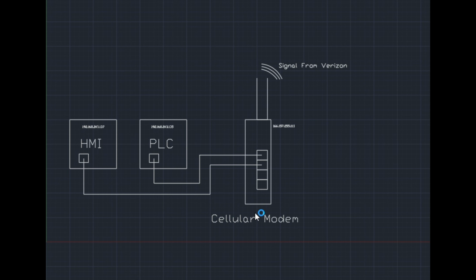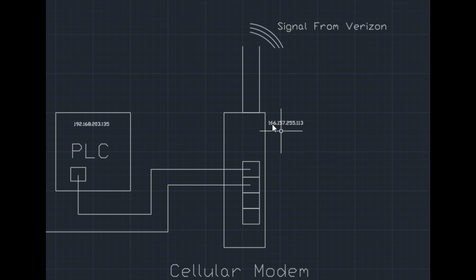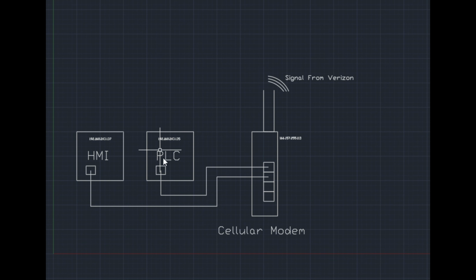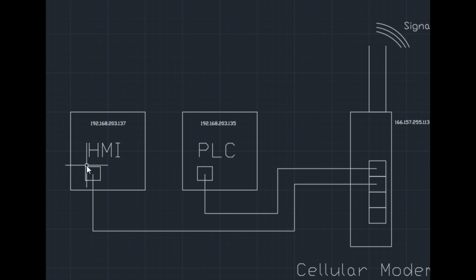So this is how our network is set up. We have our cellular modem here with our signal from Verizon. It's sitting on this IP address right here, just our 166 IP. And from that signal from Verizon, we have our Ethernet port 1 going straight to our PLC right here. It's at this IP address that was given from a range. And our second one here is going to our HMI at this IP address here, just again that range that we got.